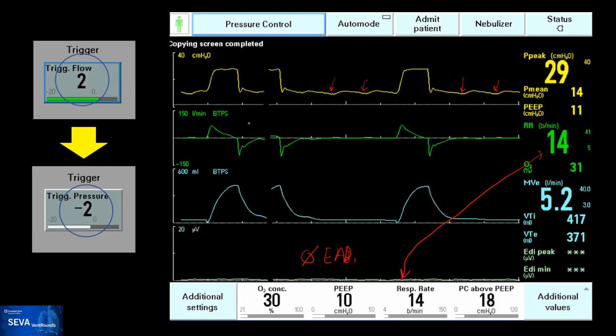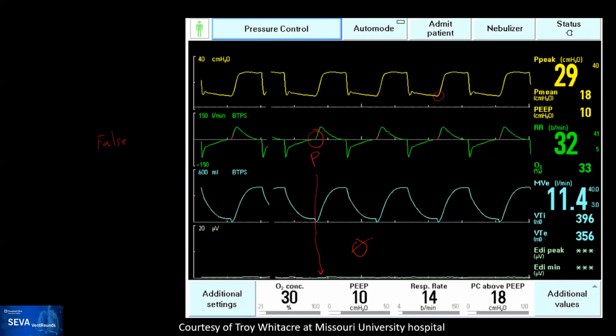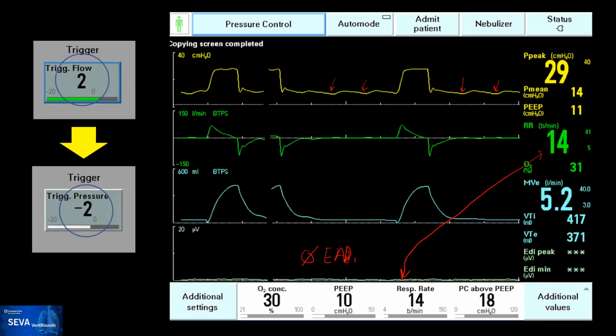So in this case, this patient was being overventilated, so probably alkalotic from overassistance triggered by a false trigger on this patient. And these are good things. I mean, this is important, I'm going to say it a couple of times: you do not need to place an electrical activity of the diaphragm catheter to detect this. I don't want that to be the message. Actually, the message for us is that a simple maneuver like changing the trigger or doing an end expiratory pause and letting it go, and seeing if there are oscillations on the pressure that demonstrate the effort from the patient, which would have looked exactly like what you see over here.